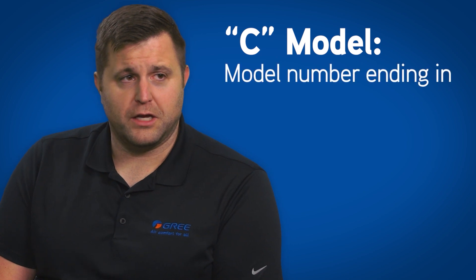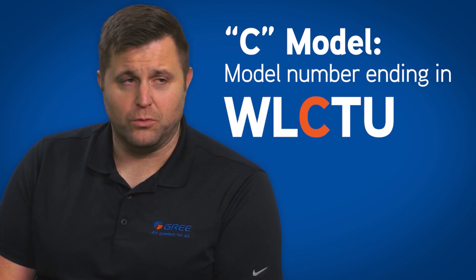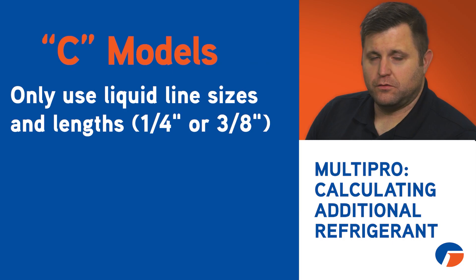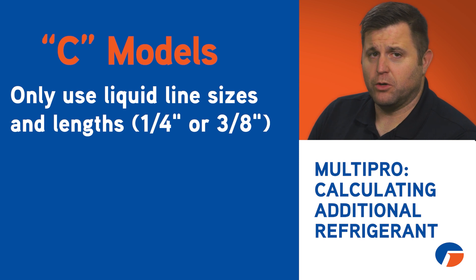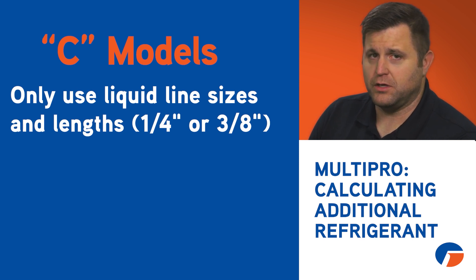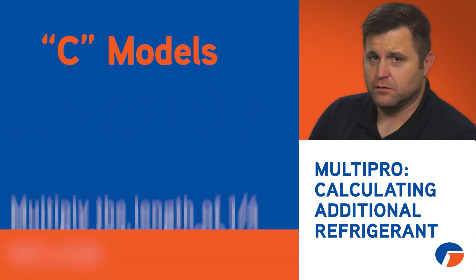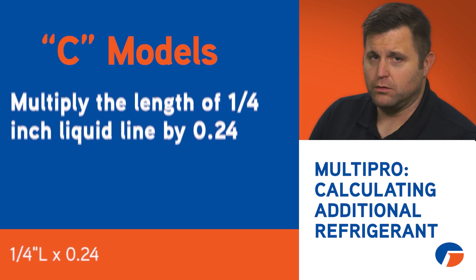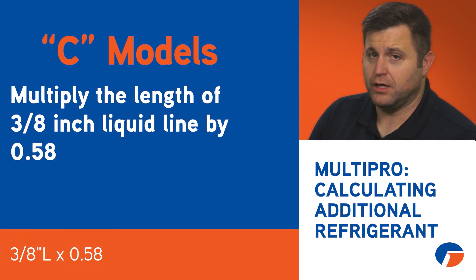For C models, as indicated by outdoor models ending in WLCTU, you'll calculate the additional refrigerant charge by doing the following. You're only going to be using the liquid line sizes and lengths, so this will only be either quarter or three-eighths. You'll start by multiplying the length of quarter-inch liquid line by 0.24, then multiply the length of three-eighths liquid line by 0.58.